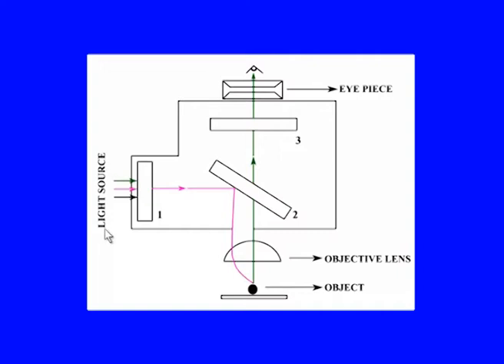In the epifluorescence microscope, there is a light source — in confocal it will be a laser. An optical filter at position one allows a particular wavelength; here it allows blue light with a wavelength between 450 to 490 nanometers. At position two is the beam splitter or dichroic mirror, which reflects light below 510 nanometers but allows light above 510 nanometers to pass through. The reflected light is focused onto the object through the objective lens.